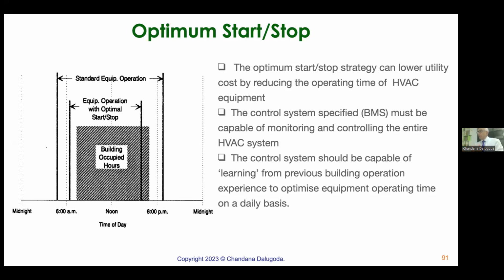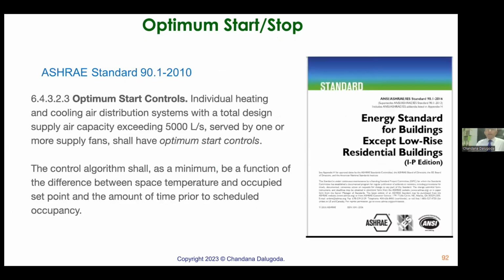The chillers won't load to maximum. But when you analyze a building running 8 to 5, with air conditioning chillers running 8 to 5 for a complete day, all chillers are working more. Let's say Monday to Tuesday, 7 o'clock we start the chillers. Thursday, Friday, normal 8 o'clock. But when you analyze, total energy consumption per week is very much lower. That is also required by 90.1.